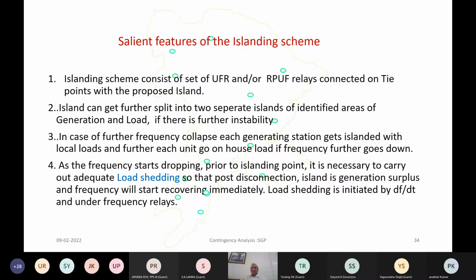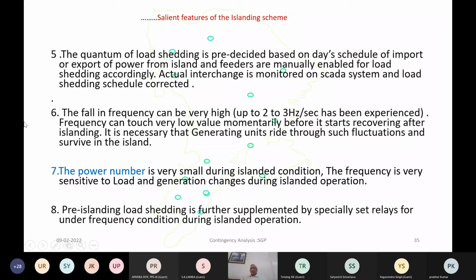So this load shedding by different means, under frequency as well as your dF by dt, the rate of change of frequency, becomes a crucial control measure to keep the balance between generation and load. Now, the success of survival depends on the quantum of load shedding, pre-decided based on the daily interchange which takes place from the island to the grid. This interchange monitoring is one of the important success factors for survival of the island. This has to be done on a daily basis, depending on the day's forecast of the load. You have to estimate how much power is being imported into the island from the grid, and then plan the quantum of load shedding so that post islanding, if islanding happens, the load and generation balance is achieved.